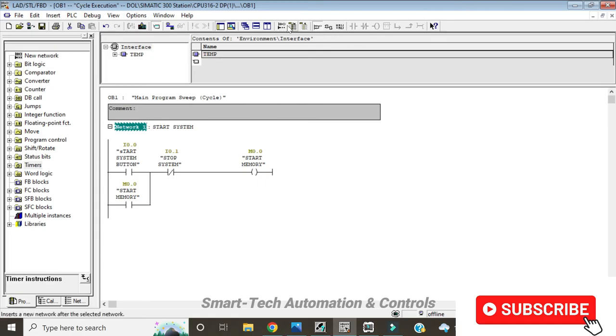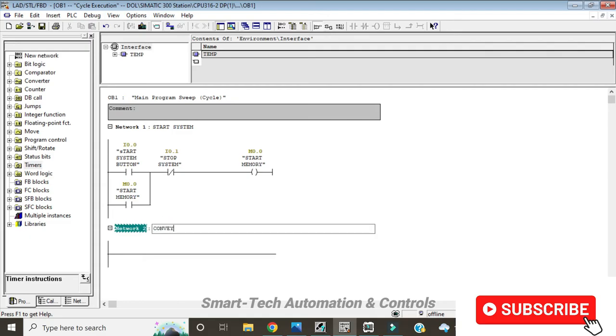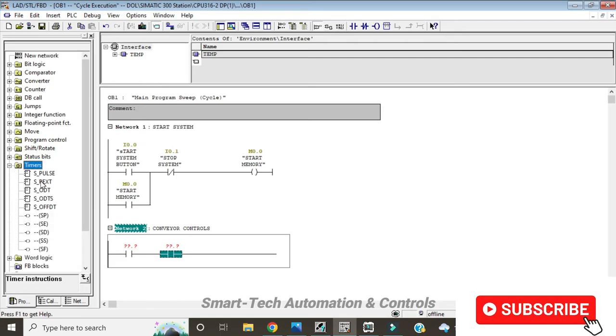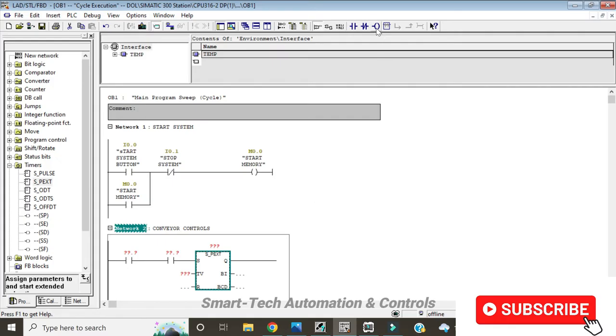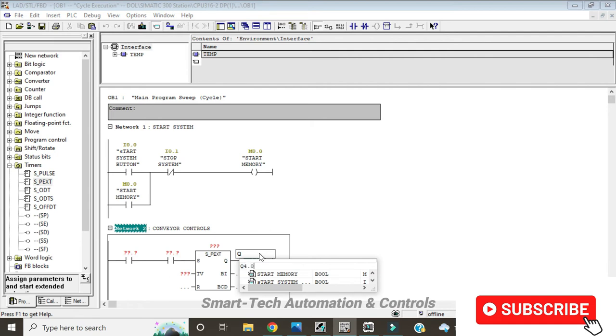I'll then add another network, and I can call it conveyor controls. On this network, I'll have two normally open contacts, a pulse timer. For the pulse timer, we come here to timers. Then I pick this one, S_pext. Then we shall have a coil. The coil here will be the conveyor motor, and we can give it address Q4.0. Then for the symbol, we call it conveyor motor.